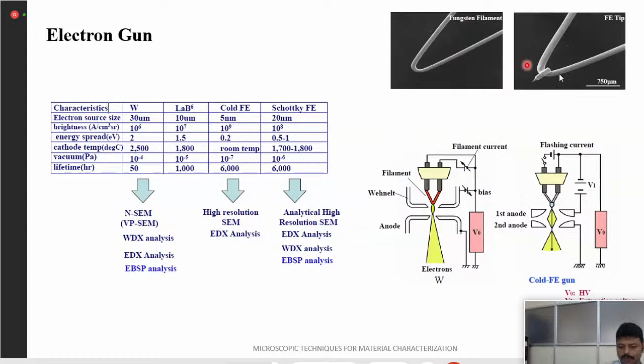Yeah, you can see this image. It's broken. The tip is broken by excessive use. It's an SEM image itself. By excessive use, the tip will break, and we can't use it further. Before breaking, we can understand that the image quality will be reduced after some 6,000 hours.